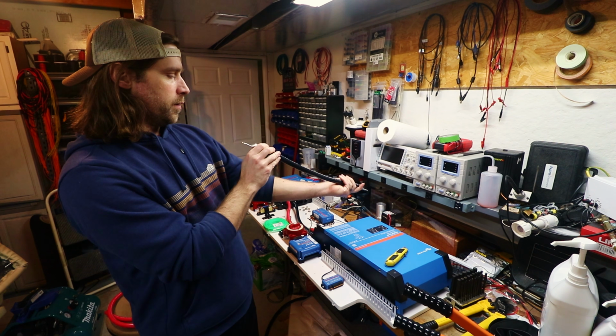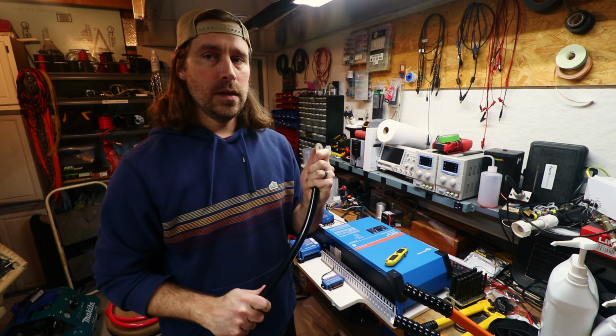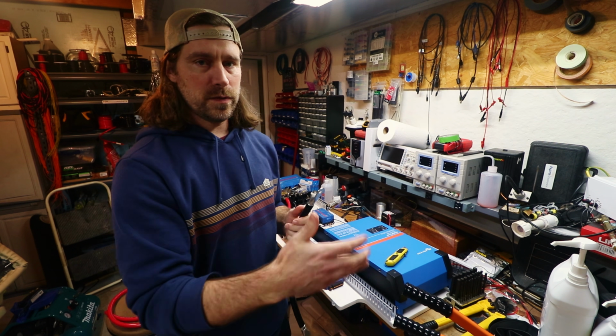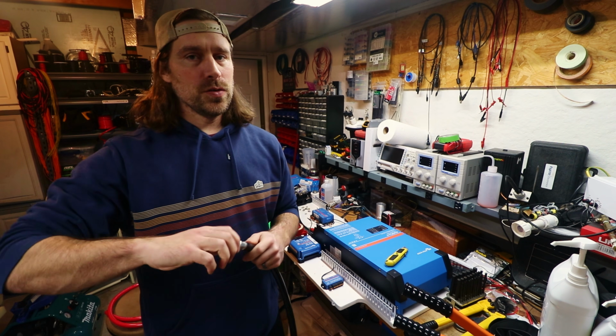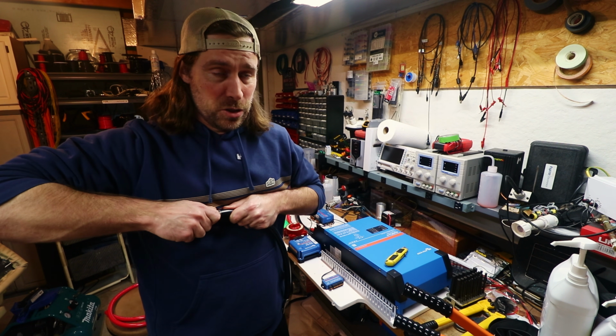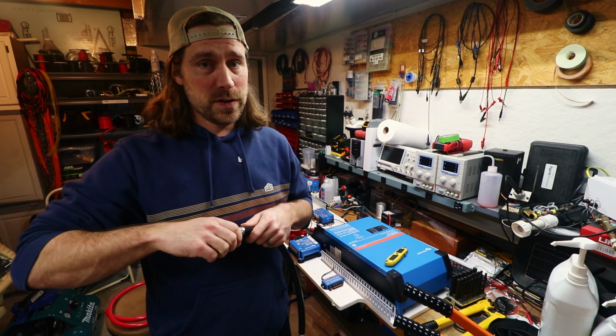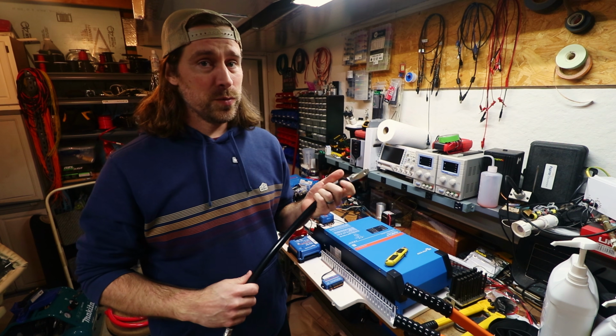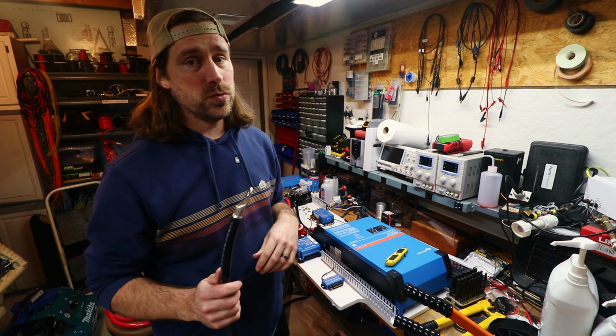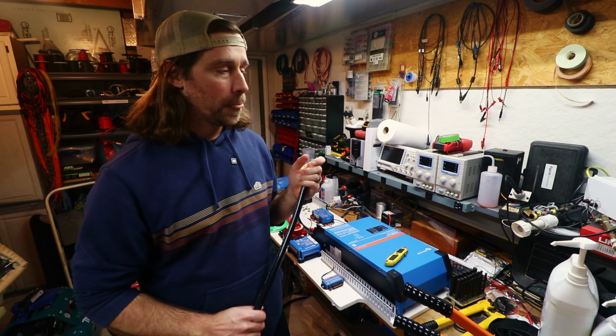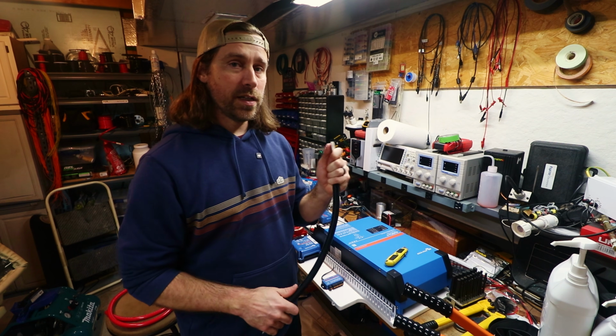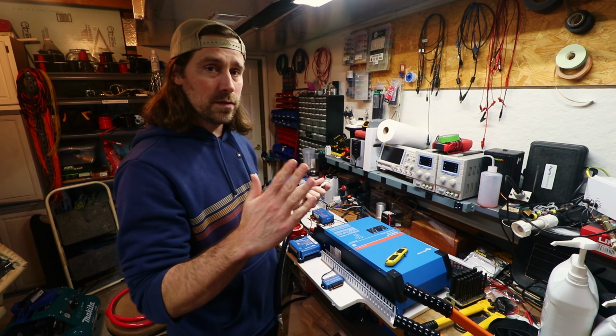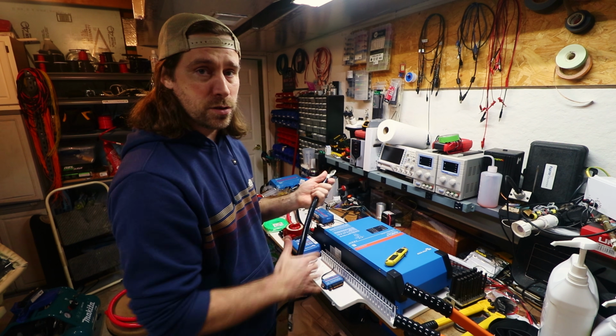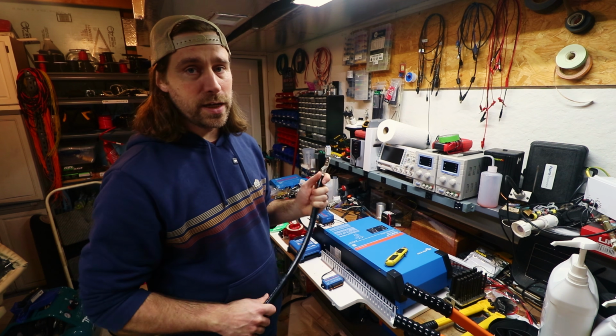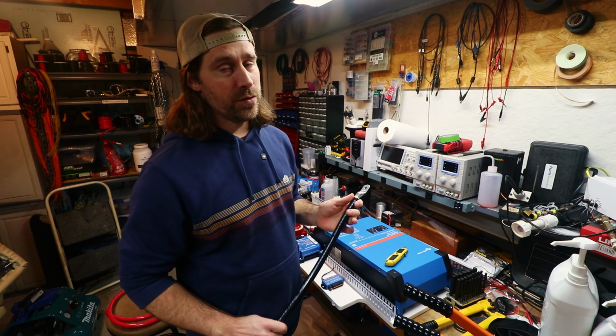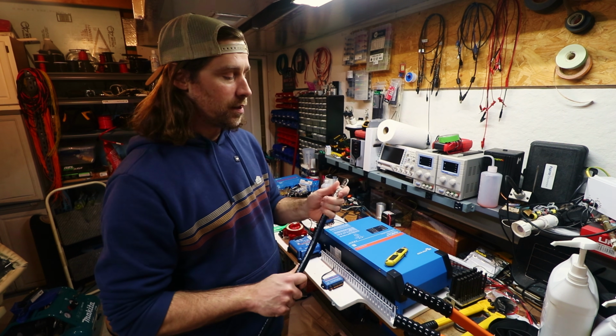All right, got those two lugs crimped on. Now, one thing I didn't talk about yet is you really should be checking the quality of your crimps before you get on a roll. The initial one, you want to check. There's unfortunately really no good way to check a 4-aught crimp. You can pull on it as hard as you want—that's a good indicator; if you can pull it off, that's really bad. But technically a good quality 4-aught crimp should withstand almost 1,000 pounds of pull force, so there's really no logistically good way to check that. But I do plan on, I have a little thermal imaging camera that plugs into my phone. Once I get all this stuff up and running, I'm planning to rev it up to the limit and take that thermal imaging camera to check all these terminals and crimps to make sure there's no hot spots. That'd be one good way after the fact to check the quality of your work. But aside from that, like I said, there's really no good way at home to check crimp quality. Take that for what it's worth.